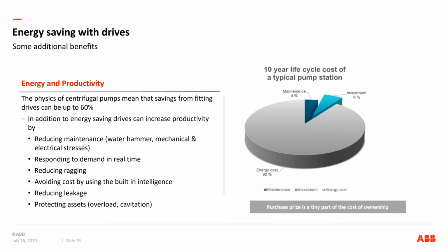Instead of running that pump at full speed, Mike talked about how they first went with some throttling valves, and that's another fantastic solution where you've got great applications that work with valves. But then you have the pump pumping 100% of its speed, 100% of its flow, against a partially closed valve. So it's wasting all that energy, creating more pressure behind the valve. That means the pipe behind the valve is going to see more pressure, and that's going to put more mechanical wear and tear on the pump, the seals, the bearings, the impeller, and then on the valve itself and the pipes that it's connected to.